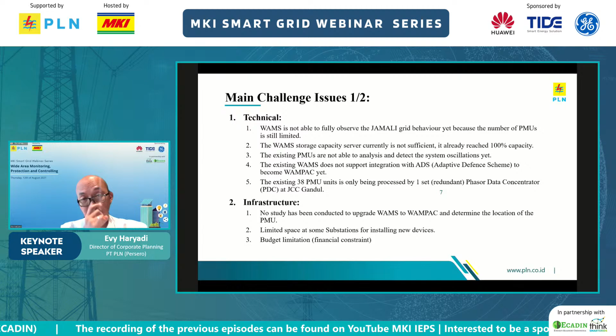Fifth, the existing 38 PMU units are only being processed by one set now, a redundant phasor data concentrator at JCC Gandul. Another issue is related to infrastructure: until now, no study has been conducted to upgrade WAMs to WAMPAC and determine the location of the PMUs. There is also limited space at substations for installing new devices.